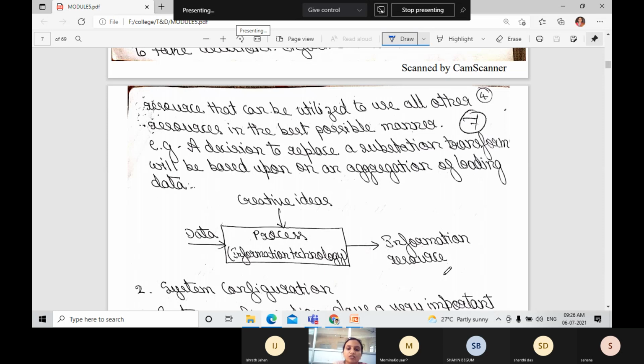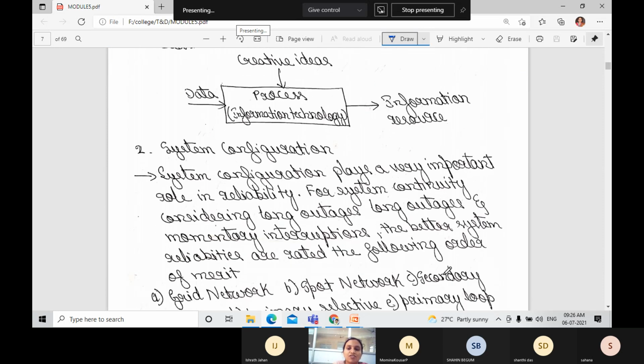Next is system configuration. System configuration plays a very important role in reliability, for system continuity, considering long outages and momentary interruptions. For example, in summer days or rainy seasons, they will do power cuts. We scold them, asking why they cut it, but they want to save the people. Sometimes there may be damage to the overhead lines, or lightning occurs, and a transformer may get damaged due to the lightning.